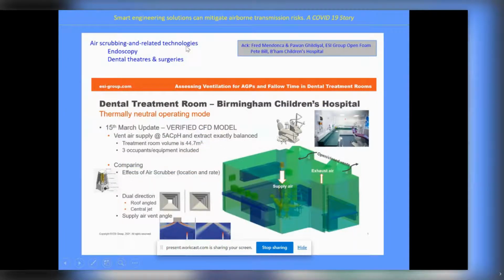This is a model we set up with Pete Bill, consultant clinical scientist at Birmingham Children's Hospital. In the slide, top right, a photograph of what the dental theatre looks like. On the left, a CAD diagram of a treatment couch, equipment, and a couple of people. The main graphic in green shows that CAD-CAM model with air coming from a duct in the ceiling and exhausting to one side of the room back through the ceiling. So already we see that's not the smartest way of ventilating a room.